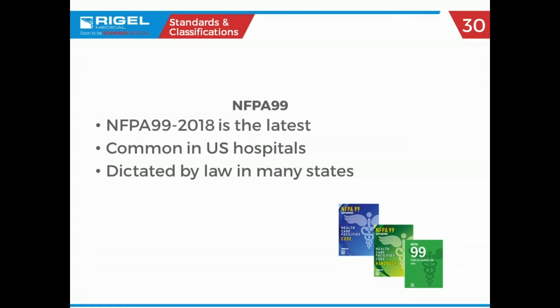Yeah. So only a couple of slides on 62353. And now we'll go more into what we typically use here, NFPA 99. So 2018 is the latest revision. They roll it, as we've talked about before, every three years. It's the most common one used for U.S. hospitals. And the interesting thing here is I think there are 32 states that say by state law you have to use NFPA 99 as your test in the hospital facility. I don't know about Washington. I know California says it. But when you think about the speed of our government systems, they probably have you testing to NFPA 99-1997. They just don't get around to updating that stuff, right?